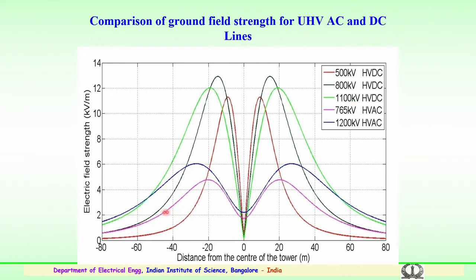For HVAC, you can see the fields are substantially less here, around 4 to 5 kV per meter, and in case of 1200 kV, it is hardly around 6 kV per meter. These are done with the proper transposition of the conductors. Again, this would reduce the field drastically. So, comparing 1100 kV HVDC and 1200 kV HVAC, or 800 kV HVDC and 765 kV HVAC, you can see the electric fields will definitely be higher, slightly higher, in case of HVDC, and for HVAC with proper transposing, the fields will be lesser.